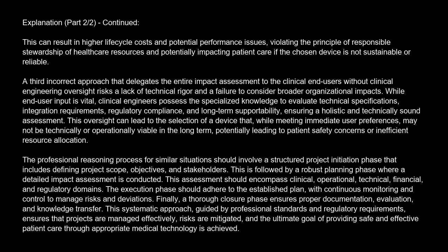A third incorrect approach that delegates the entire impact assessment to the clinical end users without clinical engineering oversight risks a lack of technical rigor and a failure to consider broader organizational impacts. While end-user input is vital, clinical engineers possess the specialized knowledge to evaluate technical specifications, integration requirements, regulatory compliance, and long-term supportability, ensuring a holistic and technically sound assessment.